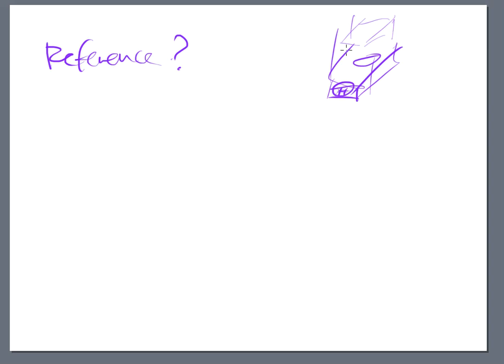Well, we talked about that, right? We said one of the ways that we do that is with calibration. And we have calibration weights that we can put onto the balance pan to double check it's giving me the proper number. And if it's not giving me the proper number, there's an internal calibration that it does. So it tries to reset itself every time. It says this is 20 grams, and this is what 20 grams is supposed to weigh. So I'm going to give you 20 for this kind of measurement. That is the purpose of a calibration. That is a reference point, right?